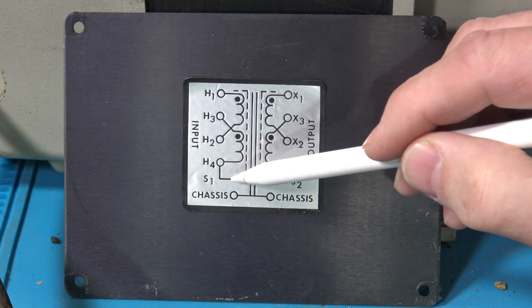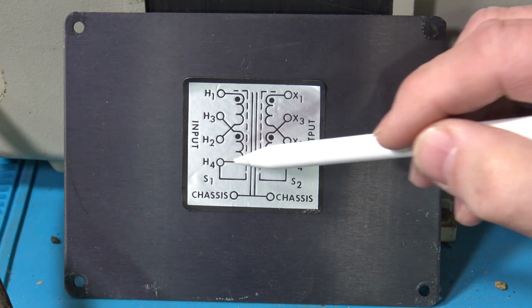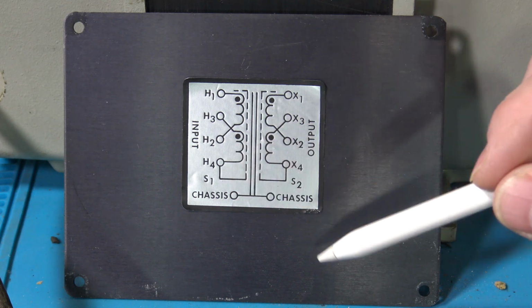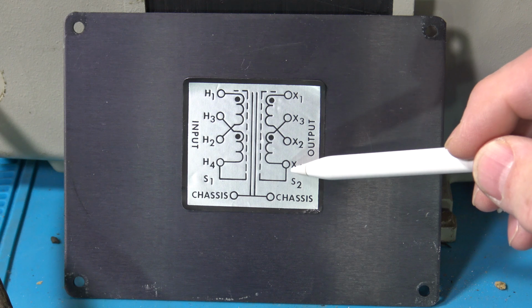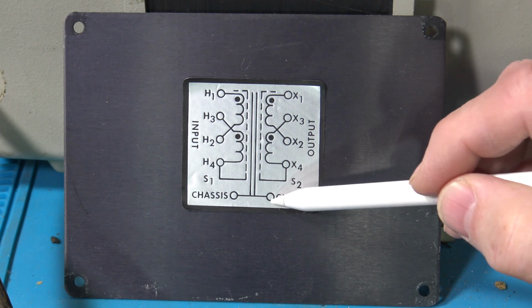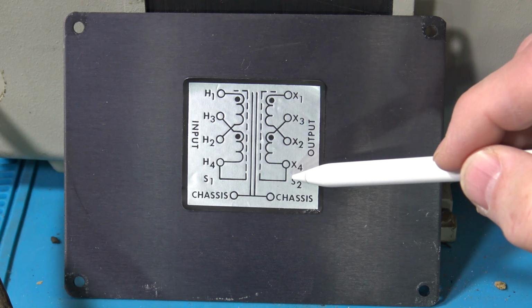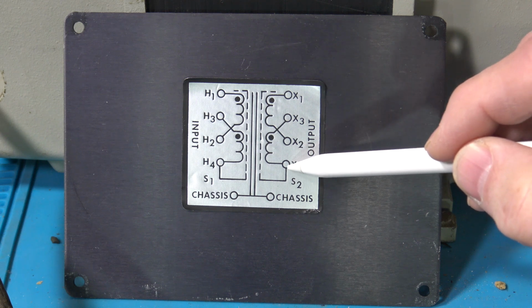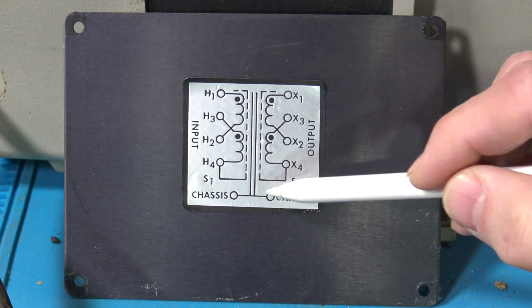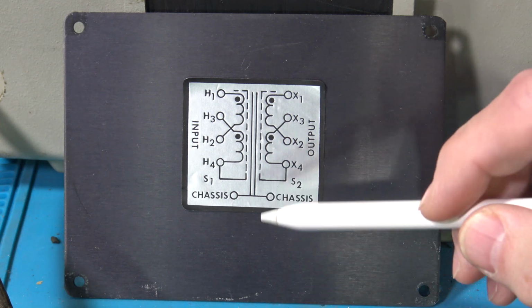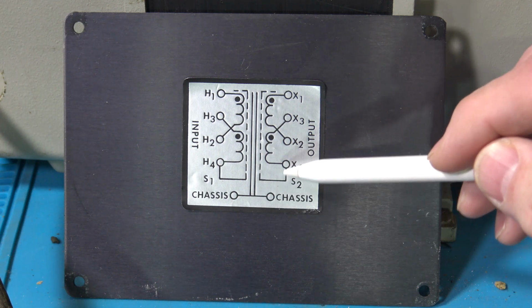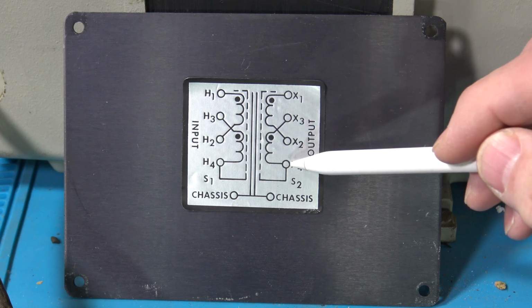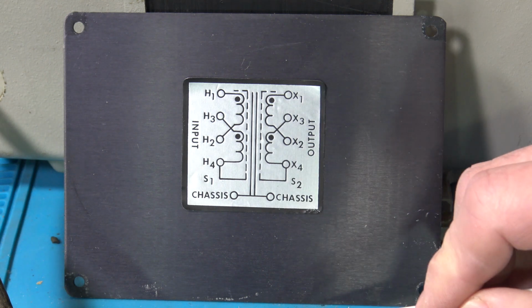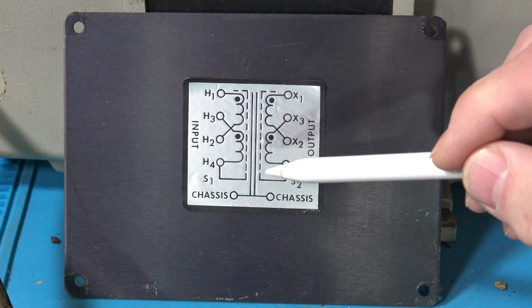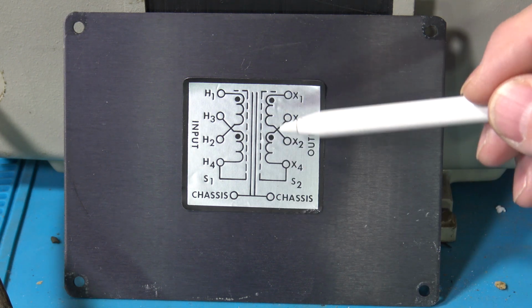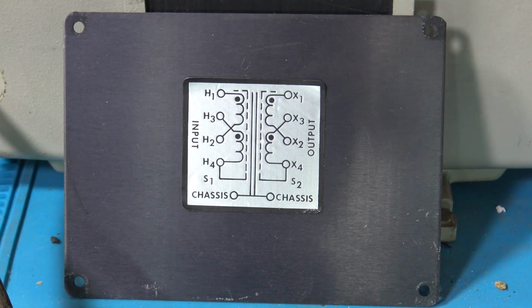Now, we also have these screens, and they're tied to one of the windings, and then that also gets tied to chassis. So that's kind of an interesting thing. We might want to tie the screens just to the chassis and not to the windings, because we don't want our winding tied to chassis, right? Because if chassis is the third prong, the ground, the safety ground, then we don't want to bond. If this, say, turns out to be line and neutral, we don't want neutral bonded to that. So we would want to open that. And maybe somebody had a wiring problem, and that's what caused the black wires to be charred. But let's check them out and see what we got.